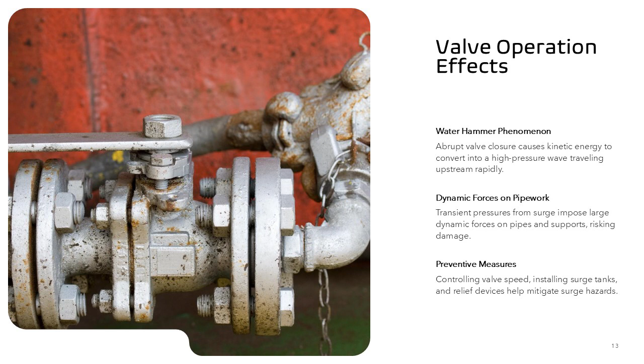Surge events are particularly hazardous in liquid systems, where incompressibility amplifies pressure spikes. Preventive measures include controlling valve actuation speed, installing surge tanks or arresters, and using specialized relief devices. Understanding surge dynamics is essential for designing systems that can withstand transient loads and avoid catastrophic failures.